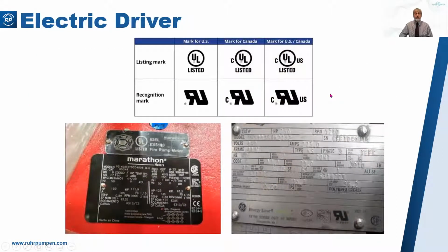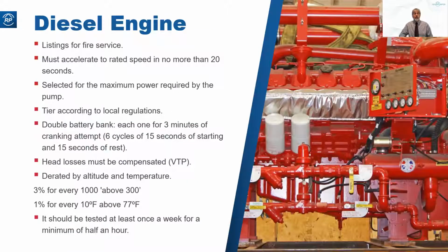There's a certification nameplate. Diesel engines should also be UL listed, FM approved. There is a requirement within NFPA-20 on the starting system. It requires 2 sets of batteries, each rated for 6 cycles of 15 seconds cranking and 15 seconds rest.